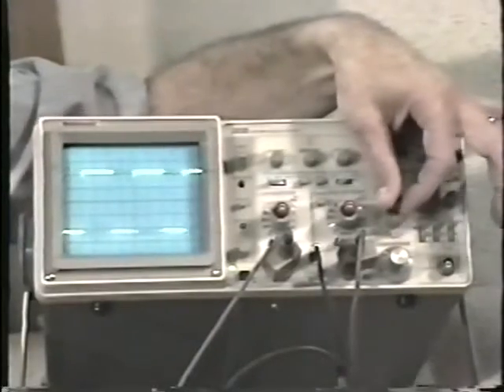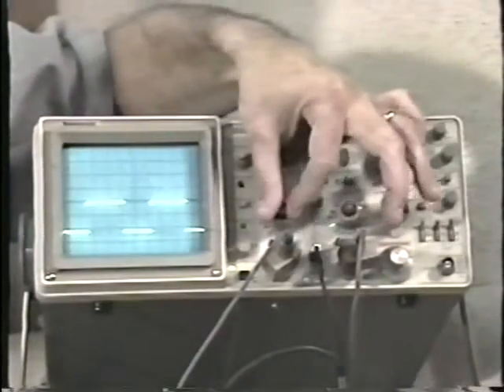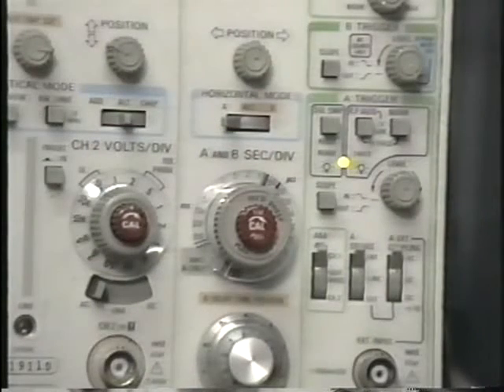This same control acts like a variable knob, in the same manner as we saw when we were looking at the vertical volts per division. Remember how it also had a calibration knob right in the center. The horizontal sweep also has a calibration control in the center and a detented, locked-in, calibrated position. Again, there's almost no reason for you to take this out of its calibration position, and you can get in a lot of trouble if you're making periodic waveform measurements and you don't have the horizontal sweep control in its calibrated position. So make sure that it's in its calibrated detent before you start making any periodic waveform measurements.